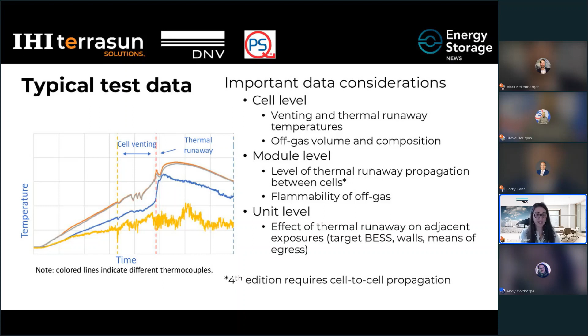Thanks, Carrie. So what can we do with all this test data we get out of the UL9540A tests? Well, as Carrie mentioned, we had some important data, including temperatures, gas compositions, and gas volumes. At the cell level, a lot of the considerations can be given to BMS monitoring and alarm considerations. So that is setting different alarm temperatures, setting different cutoff temperatures. So the BMS is meant to protect the cells from damage. So if the BMS detects any temperature or electrical anomalies outside of the normal operating conditions of the battery, it can take action to disconnect the battery to prevent cell damage and potential thermal runaway.